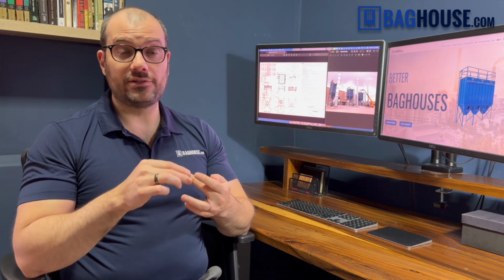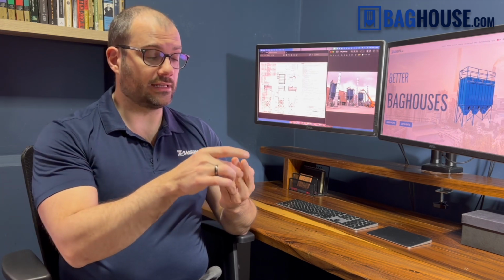So for example, we recently were at a manufacturer that makes things out of wood, and we identified a few systems where they have a FlameX system, so they have a spark detection and extinguishing system, and then they had explosion venting on their baghouses. They asked us to review it. Well, we were able to identify that they only have 2 of a number of things that are usually required by the NFPA. Because they were recirculating the air back into the building, they did not have any sort of explosion isolation on either the inlet, the dirty air going to the baghouse, nor on the clean air return coming from the baghouse back to the building, which is a crucial requirement in the NFPA standards. They also had no fire protection for the air coming back into the building.